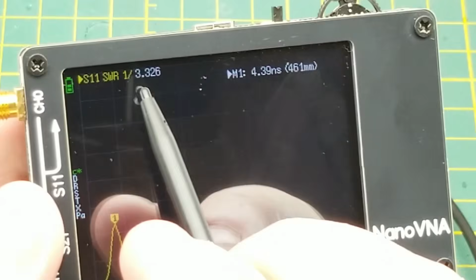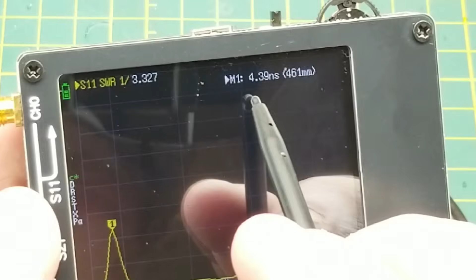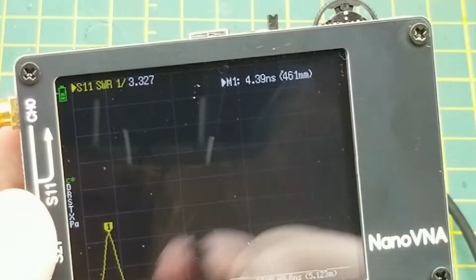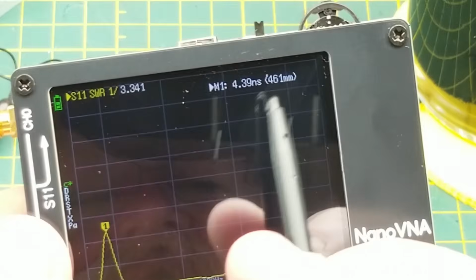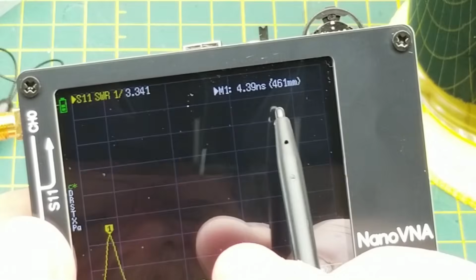And in this case, we can see the obvious spike of high VSWR, 3.3 in this case, and that works out to 4.39 nanoseconds or 461 millimeters. According to the scale on my desk, my mat is 43 centimeters wide, and this is very, very close to that. So if you're hunting for an error in your transmission line, being 3 centimeters off would make it fairly easy to find. That's less than the width of your hand. Of course, on a longer line, it wouldn't be quite that precise, but still, it's going to get you within a couple of hand widths of where your error is.